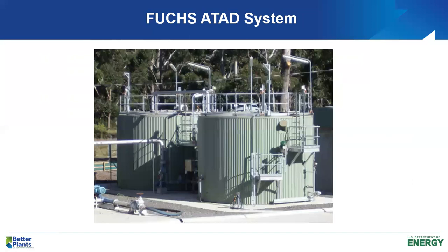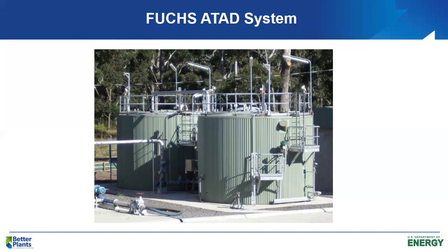Two actual ATAD tanks are generally operated in series. They can achieve 40% VSS destruction in just 4–8 days compared to ~40 days in conventional aerobic digestion, and pathogens can be reduced to below detectable levels, enabling class A biosolids production. It's a robust but more challenging process to design and operate. Energy use is approximately 440–640 kilowatt-hours per ton of total solids destroyed.